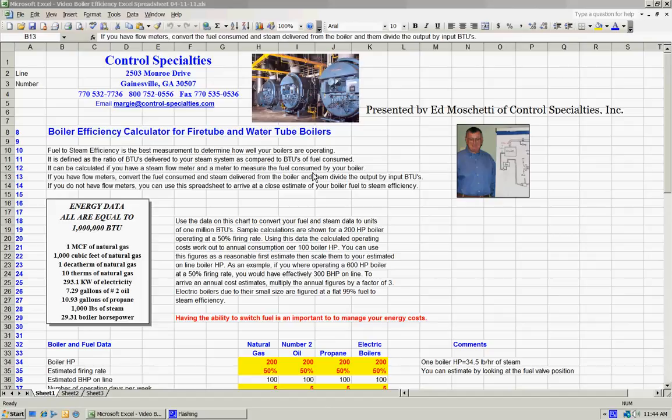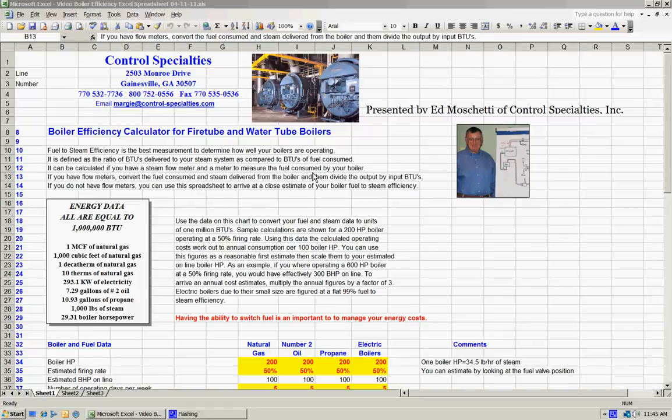And then we would measure the amount of gas going into the boiler and convert that measurement to BTUs, and then do the division output by input, and that gives us the fuel to steam efficiency of the boiler. That is really the final measure of how well your boiler is operating. In other words, how much energy is it delivering to your plant for the amount of dollars you're spending for that energy.